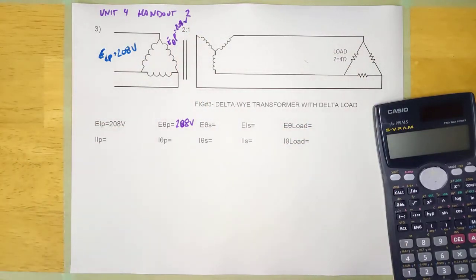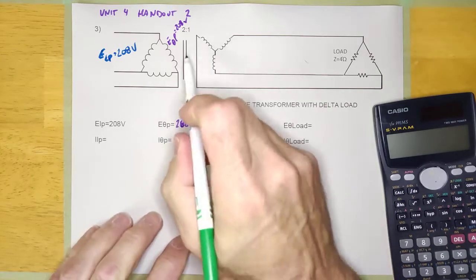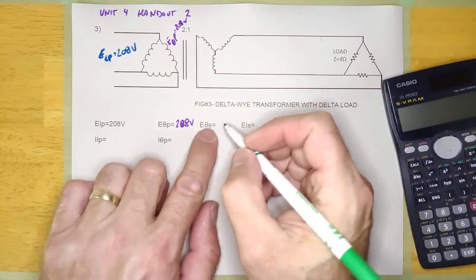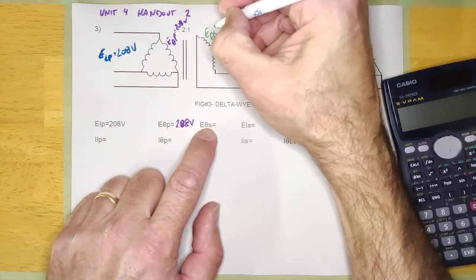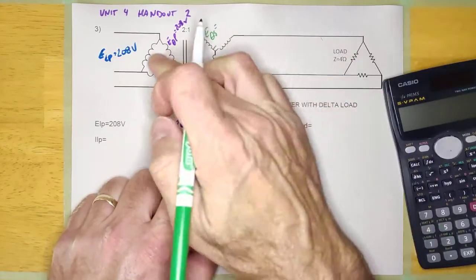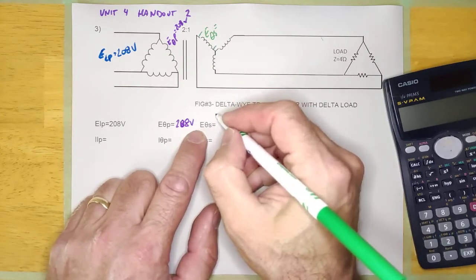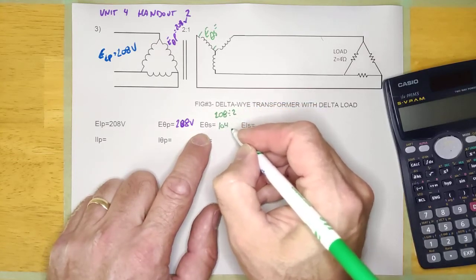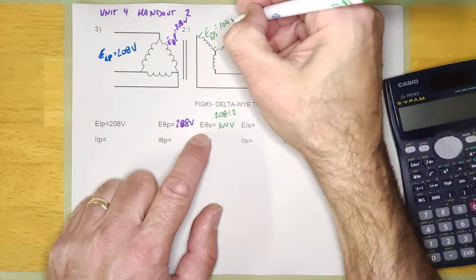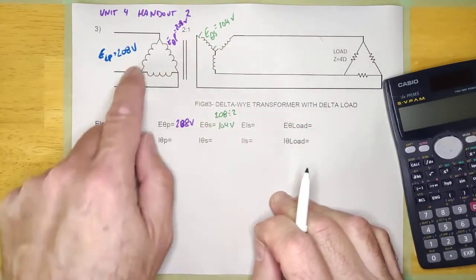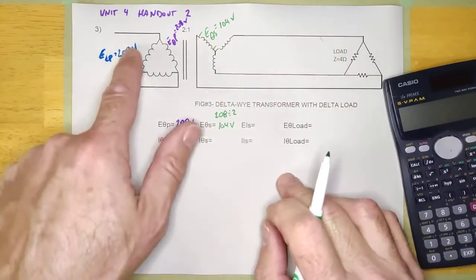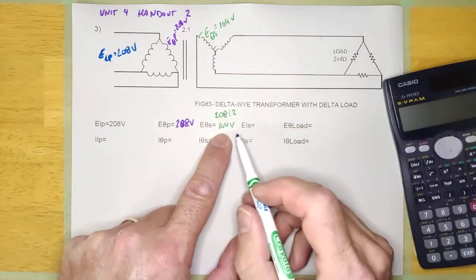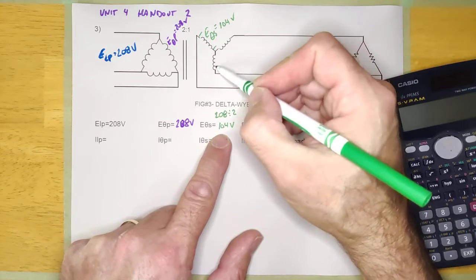Now we're going to go across the transformer. The ratio is 2 to 1, it's going to be step down. So E-phase secondary — measuring from there to there — since it's 2 to 1, I'm going to divide by 2. So this is going to be 208 divided by 2, and that's going to be 104 volts. I'm putting it in the table but also writing it right on the transformer itself — that makes it a little easier to follow.